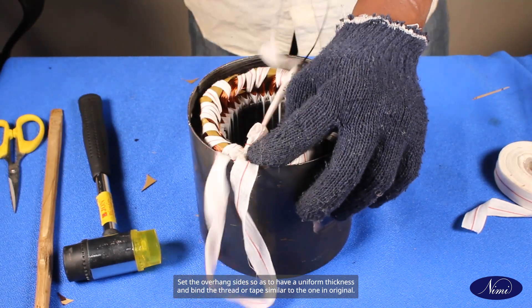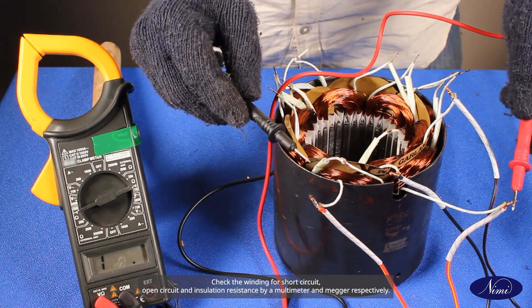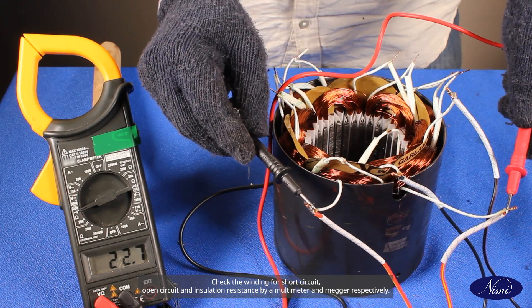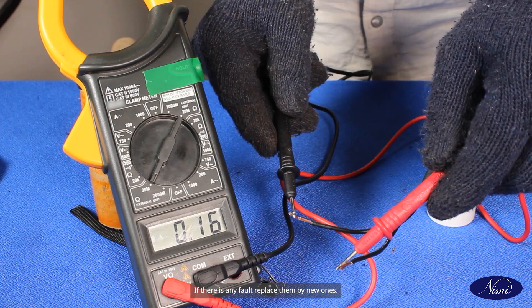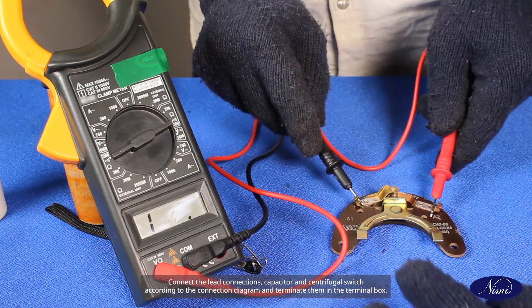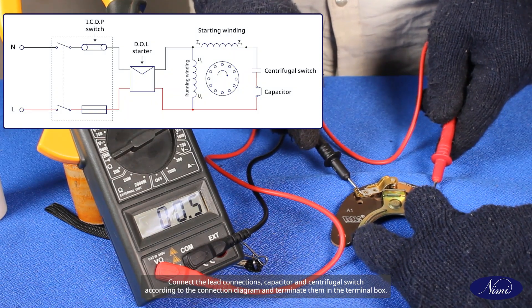Test the winding. Check the winding for short circuit, open circuit, and insulation resistance by a multimeter and megger respectively. Check the condition of the capacitor and centrifugal switch. If there is any fault, replace them by new ones. Connect the lead connections, capacitor, and centrifugal switch according to the connection diagram and terminate them in the terminal box.